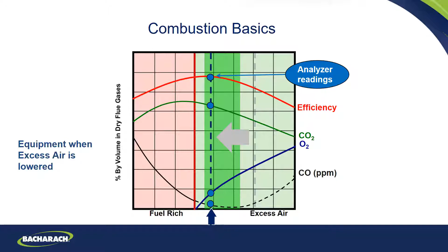But these types of boilers have a tubing that comes down you can connect to, you make it tight, and you can work with your oxygen and CO. And in this case, I can't remember what the oxygen was, but the CO was over 1,000 parts per million. It was very low oxygen. So we actually had them add a little more oxygen to the process. Because it was a coal and oil slurry, we didn't have the gas pressure. The oxygen was 6.9, that's what it was. We raised it to 7.1, not that much, but it dropped the CO from 1,000 down to 400. Back in 1983, they said that was fine. They had a stationary engineer there all the time that would work on that. So, an interesting example of big old boilers.